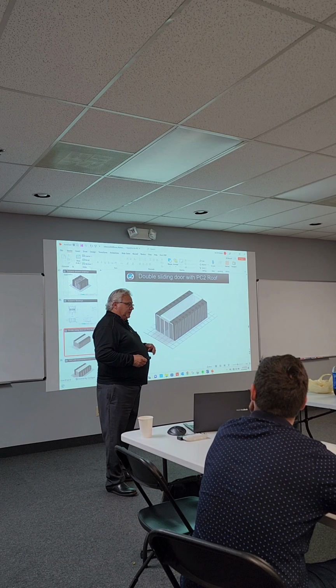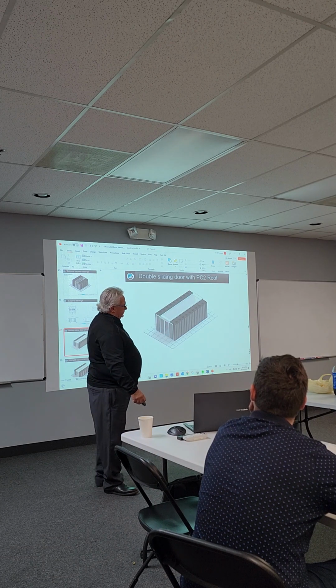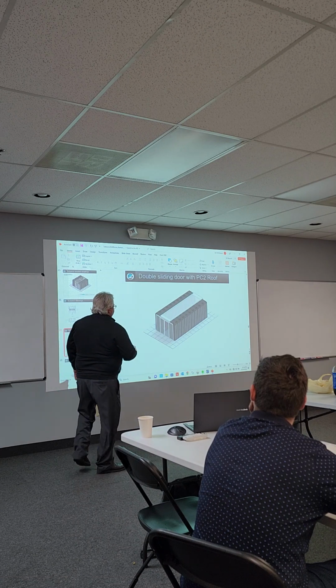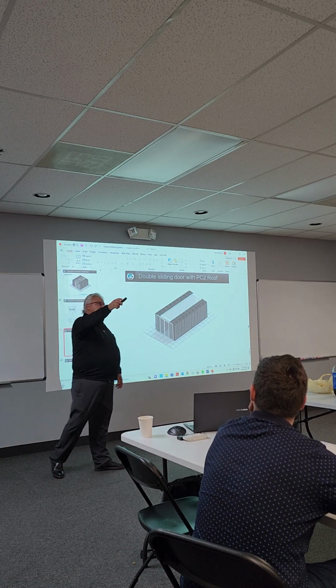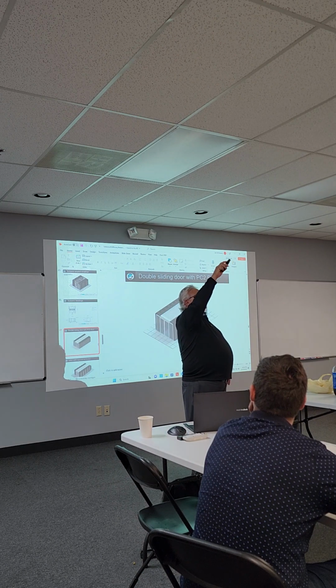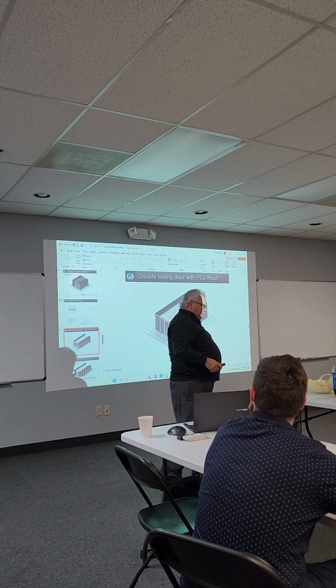You've got electric reheat in these things. That thing catches fire, melts down, the plenum melts, and it drops down on the servers. That's another thing - if you ever see a mini-mate in the ceiling with that plenum, I hate them, because basically they put air out the four sides and return it up the middle.